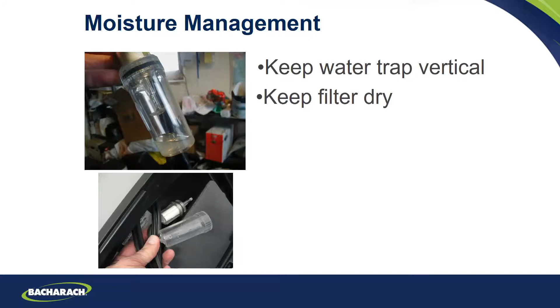If it's a wet filter and you keep operating on it, it's like sucking on a wet sponge, and you're going to pull that water into your instrument. So you want to change that to a dry filter. Let the old one dry out. And when you're done testing, you want to go into a purge mode. Okay, so you can purge our instruments for 1 minute, 5 minutes, or 10 minutes, and you set that up in your setup menu.